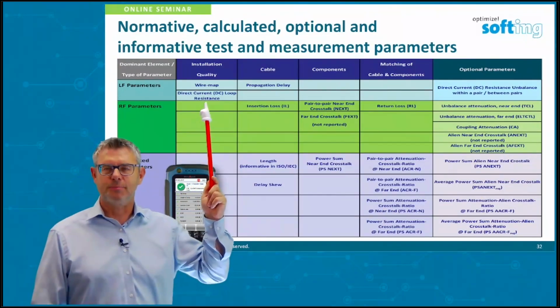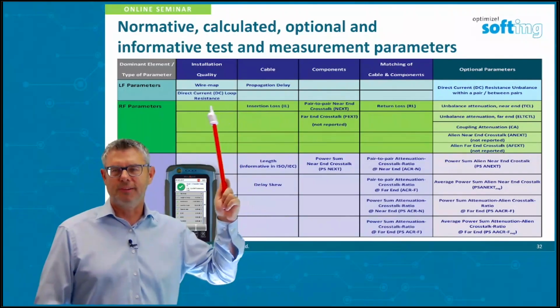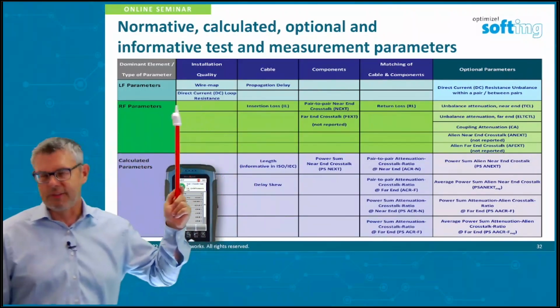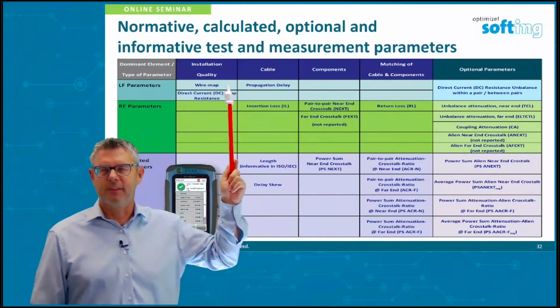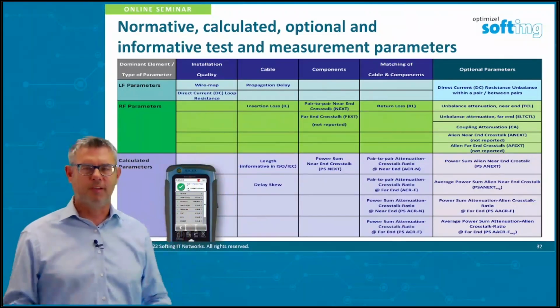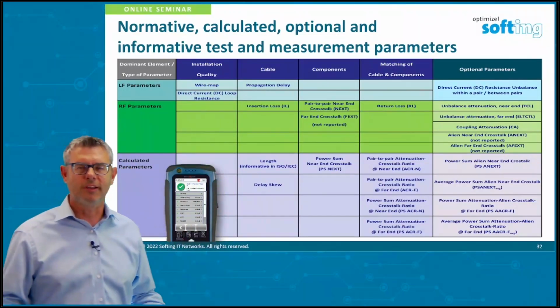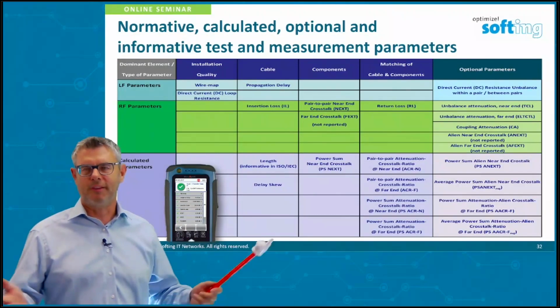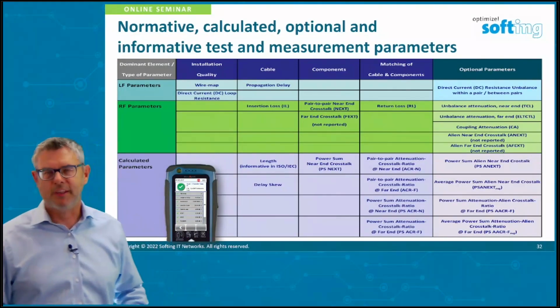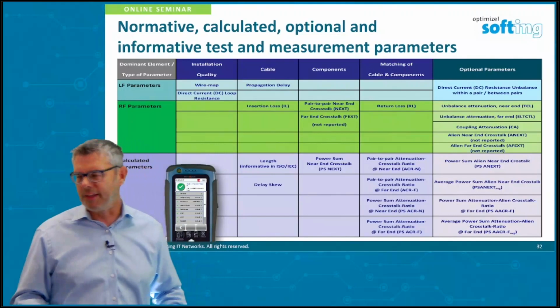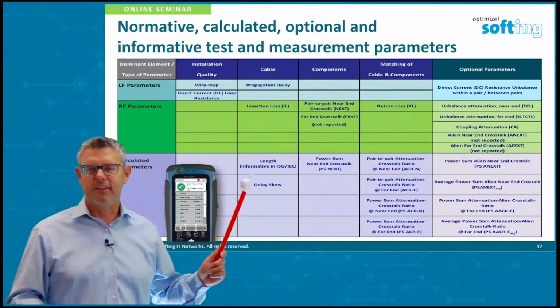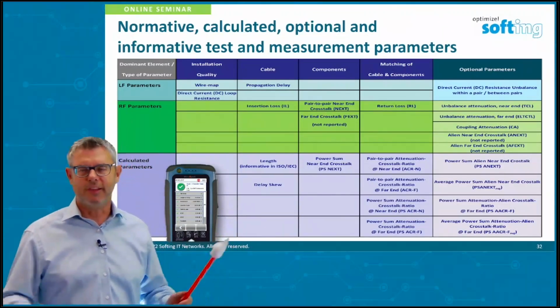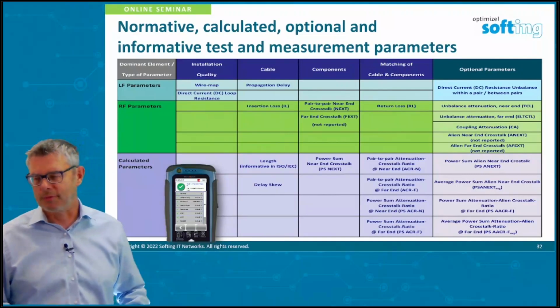What's the influencer of this parameter? There's installation quality — the wire map comes down to installation quality, so if the installer has done wrong wire mapping, it simply doesn't work. The cable gives us delay times and length indication. The connector has no length; the length indication comes from the cable.